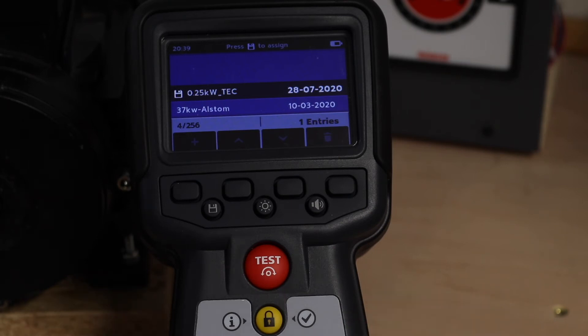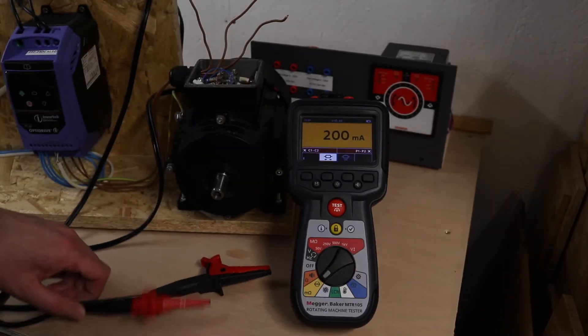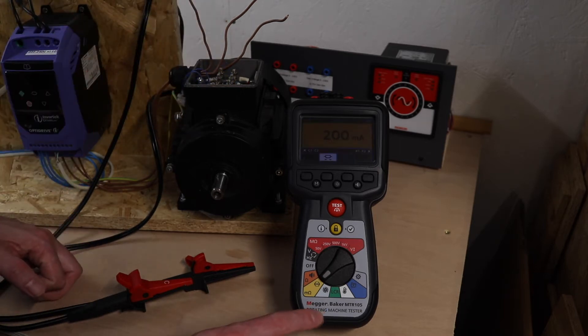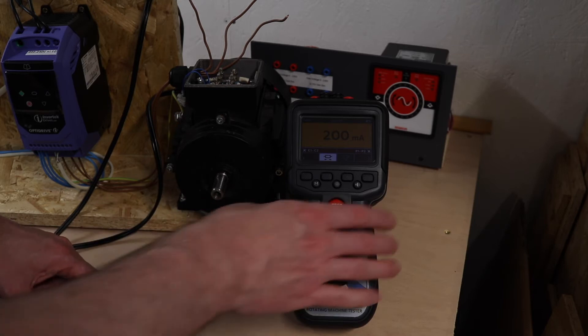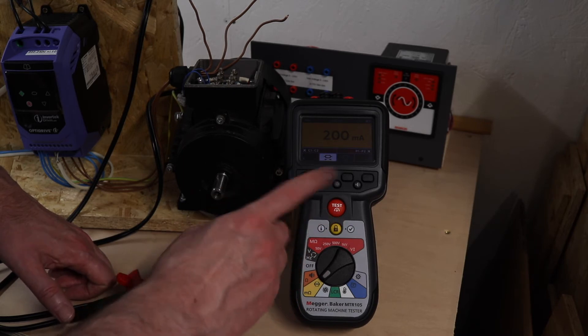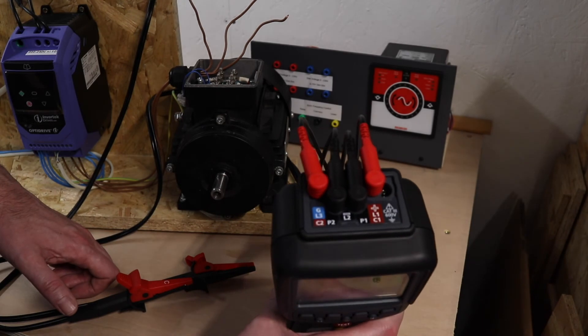Now we've done that, we can flip back to whichever test we want to do first. Starting off with dead tests, I'll do the winding resistance test first. On the Megger I have two options: a four-wire method or a two-wire method. I'm going to use the four-wire method for the winding resistance test, and then the two-wire for the earth bond. You can see the connections at the top of the instrument.